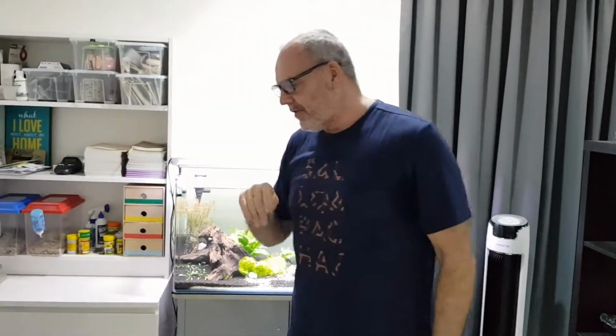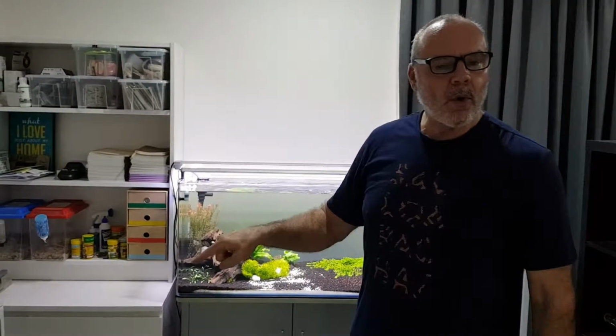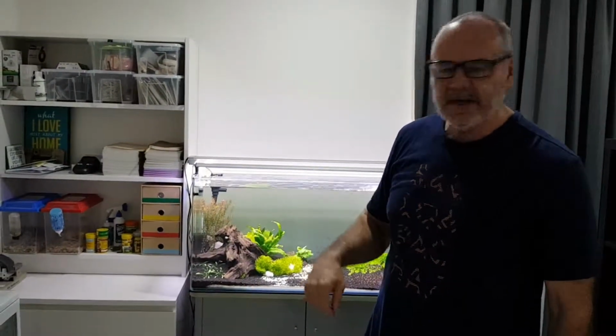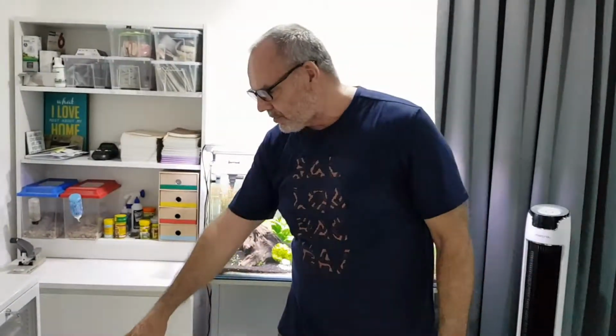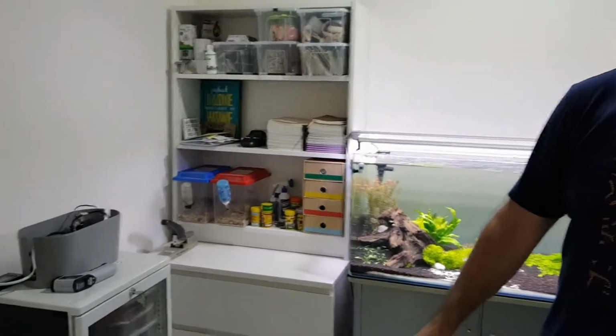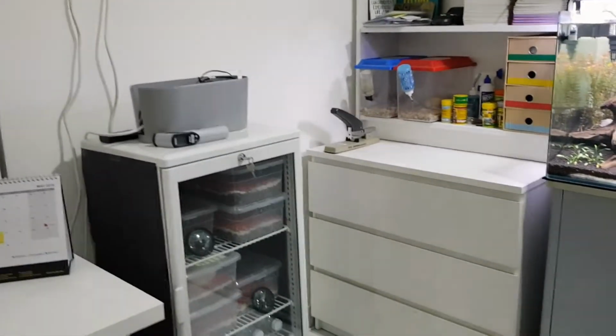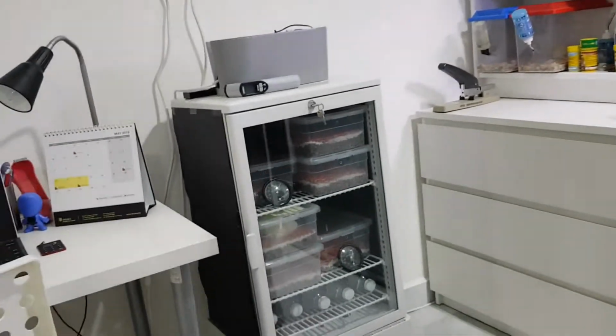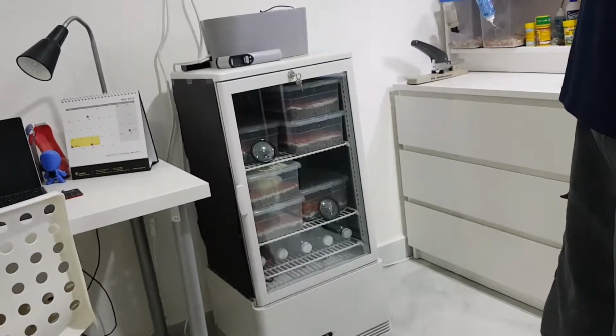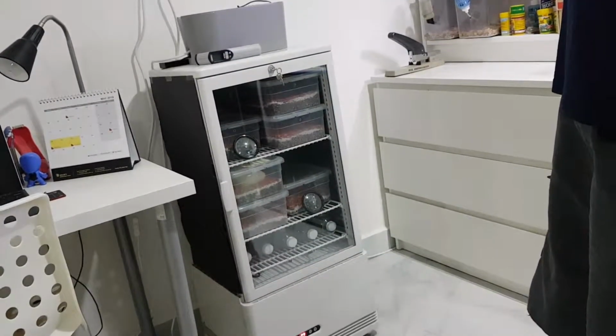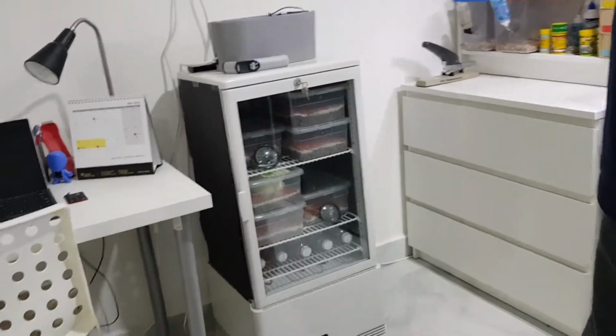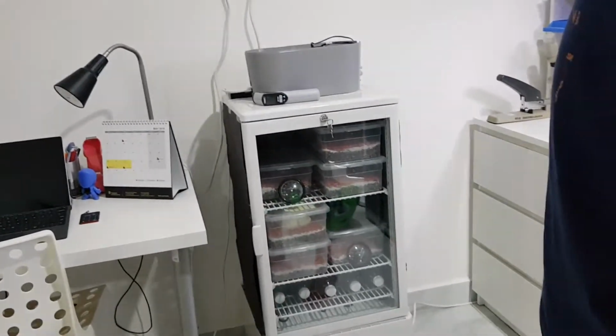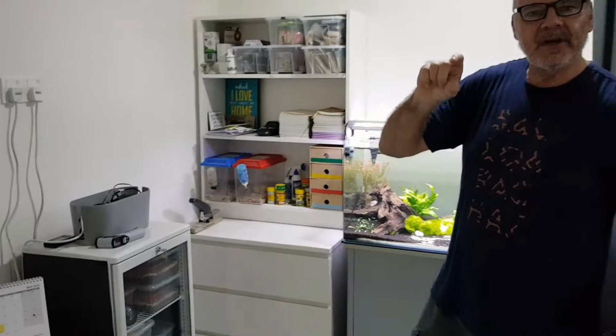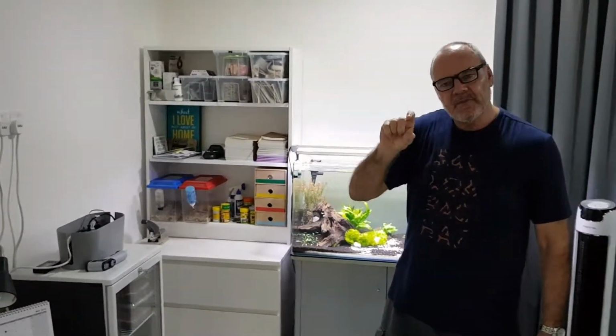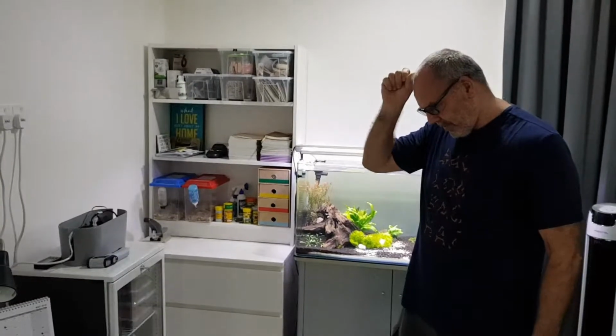So we know that if I set that thermostat to the temperature that I want, 31.6 degrees inside the incubator, the residual heat in the cables when it switches off is going to overheat the incubator. So right there we know we're going to have to set the thermostat at a lower temperature. So what I've done with my thermostat is set the difference between the on and off values to as small a window as I can get given the sensitivity of the thermostat. Sometimes it's half a degree, sometimes it's 1 degree. In this case it's half a degree, so it's set to half a degree above, half a degree below the temperature that I've set on the thermostat.